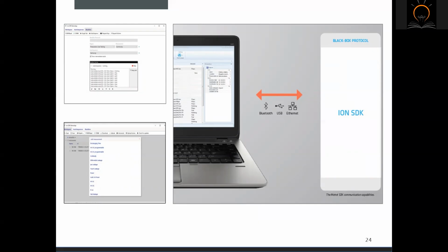SDK functionalities. The SDK also has a built-in black box protocol for online communication with the measuring instrument. Measurements can be uploaded or downloaded based on the SDK included database. Auto sequences can be uploaded and downloaded to the test instrument as well. The SDK enables access to all measurements of the measuring instrument, structure object creation, empty measurement creation, upload of a newly created workspace on an instrument, or even export to an XML.